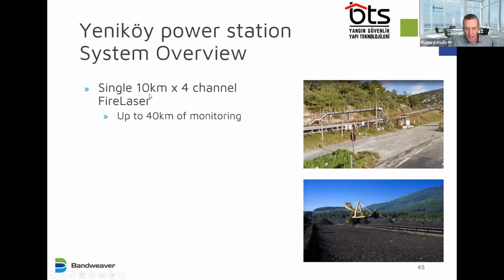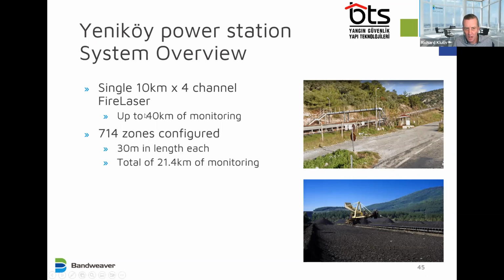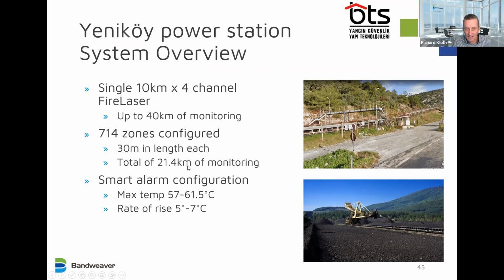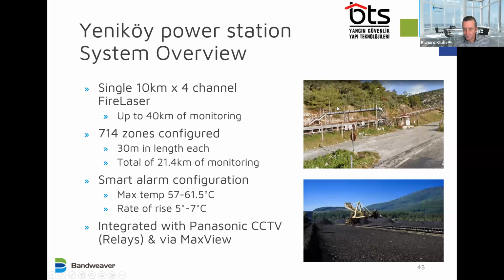So there's a single 10-kilometer 4-channel fire laser. It's up to 40 kilometers of monitoring, 714 zones, 30 meters each zone, the total of 21.5 kilometers, so 21,500 active measurement points. And they configured the alarms so the maximum temperature was 57 to 61.5, rate of rise 5 to 7 degrees C per minute. The system was integrated both with the Panasonic CCTV using relays and also using MaxView.